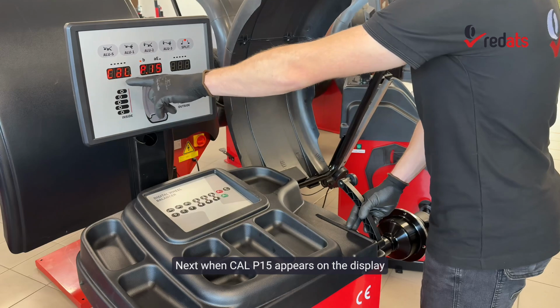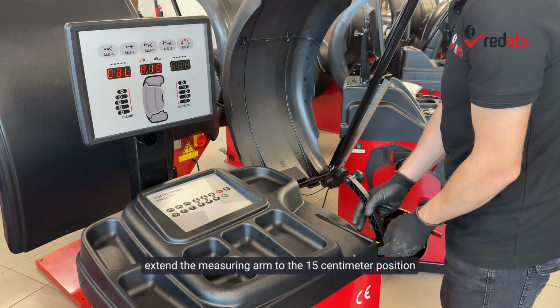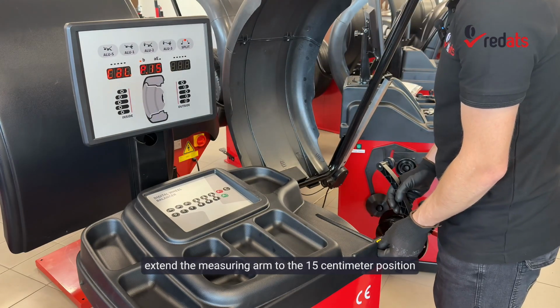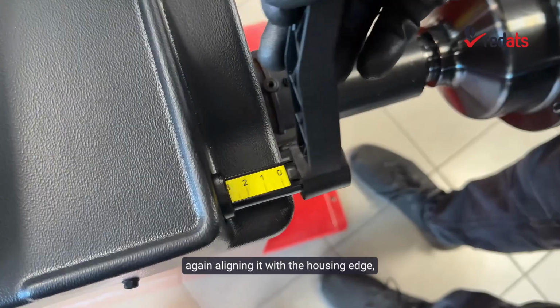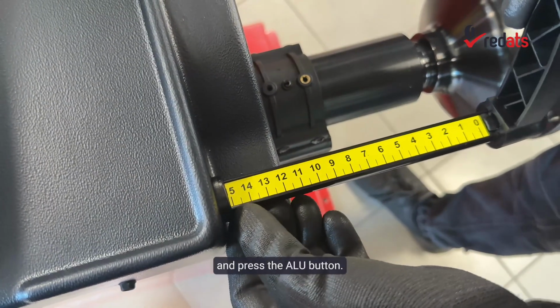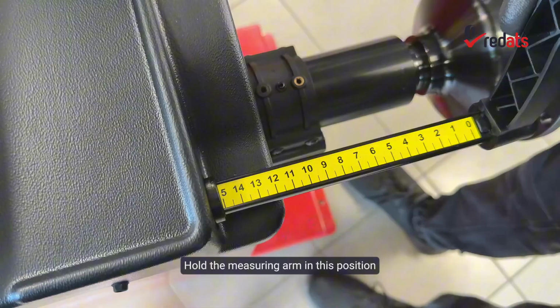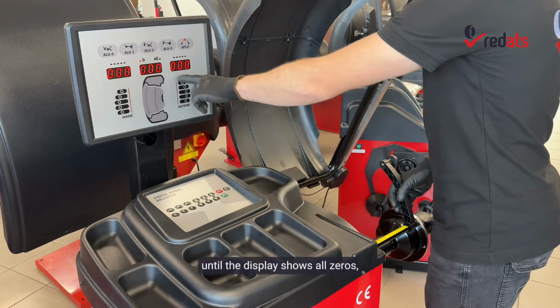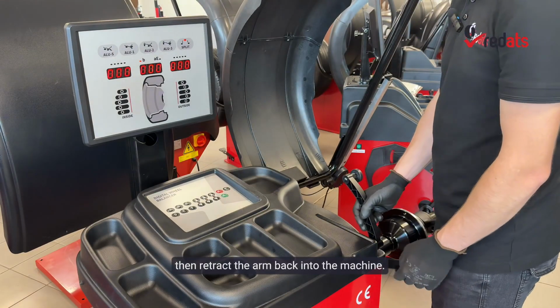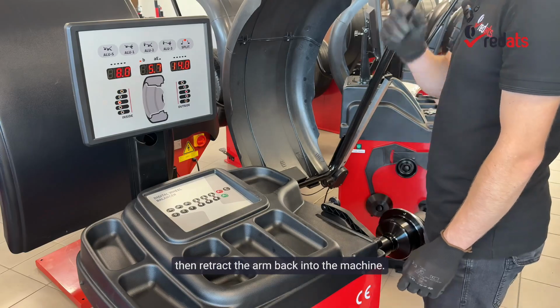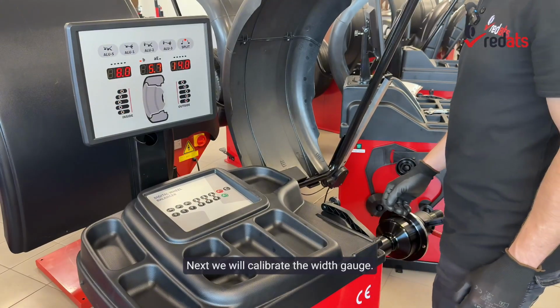Next, when Cal P15 appears on the display, extend the measuring arm to the 15 centimeter position, again aligning it with the housing edge, and press the ALU button. Hold the measuring arm in this position until the display shows all zeros, then retract the arm back into the machine. Next, we will calibrate the width gauge.